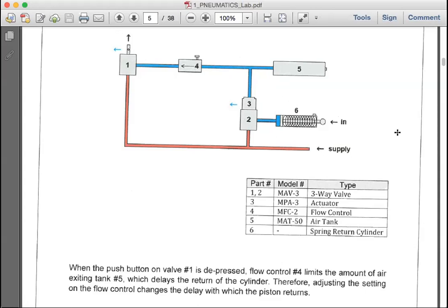It's not like the piston moves in slowly. There is a tipping point when the pressure does not activate the actuator anymore. Therefore, the actuator just deactivates, the stem pops up, and the piston returns quickly.